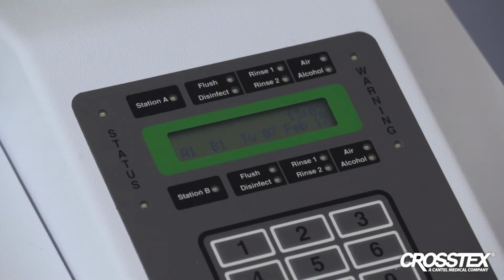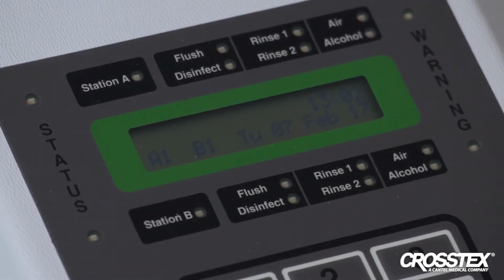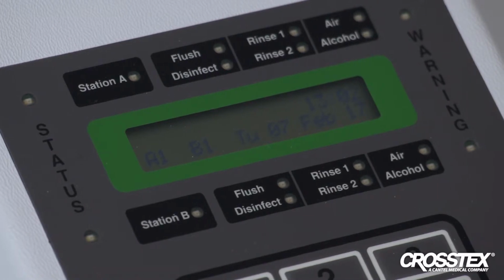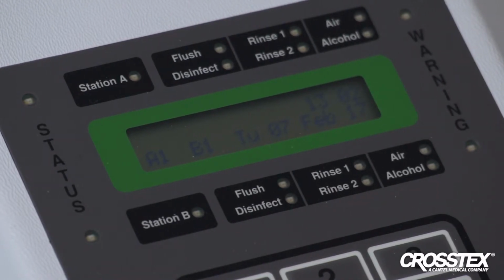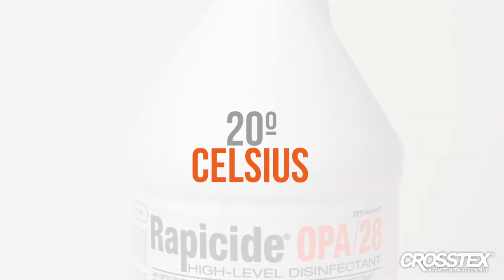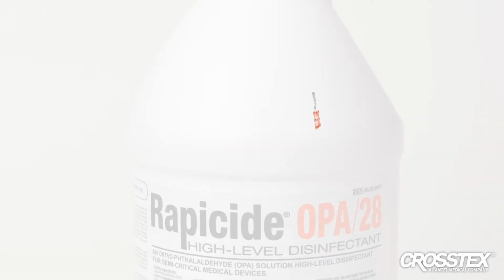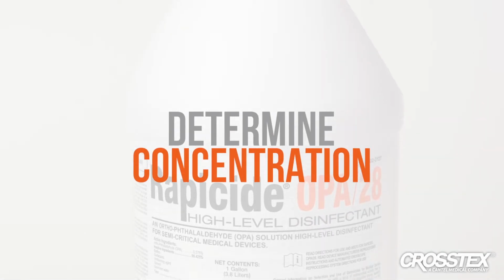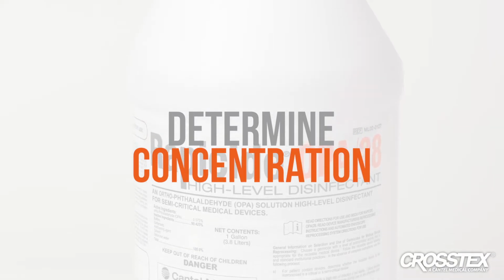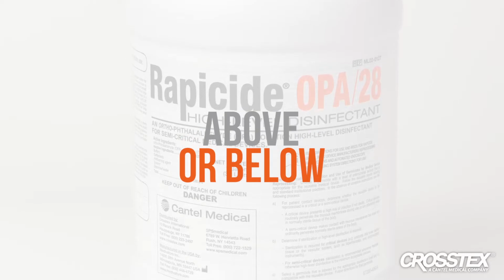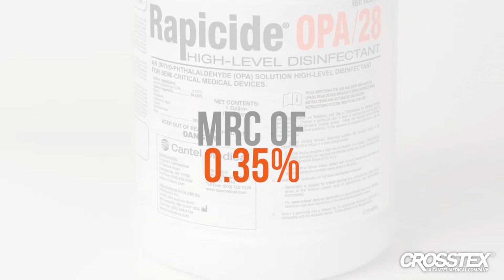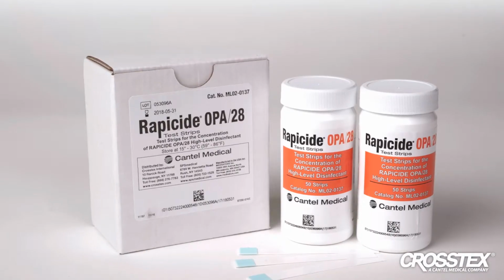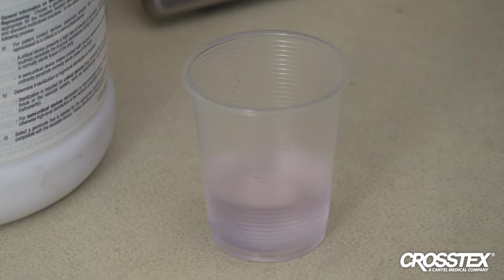High-level disinfection requires appropriate temperature, contact time, and length of use following solution activation. Always confirm the temperature of the solution in the holding tank is at least 20 degrees Celsius. Next, determine whether the concentration of OPA, the active ingredient in Rapicide OPA 28 solution, is above or below the established minimum recommended concentration, or MRC, of 0.35% by using Rapicide OPA 28 test strips.